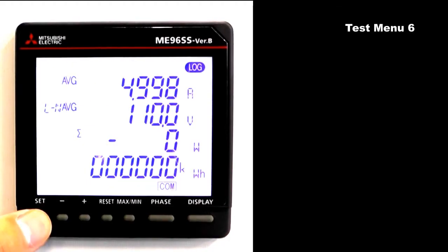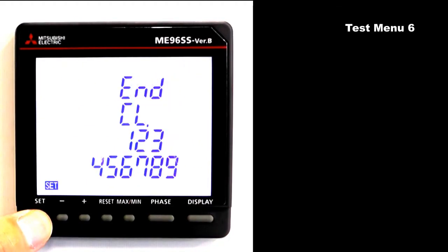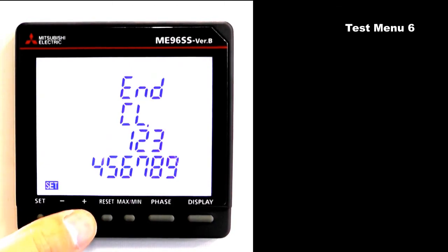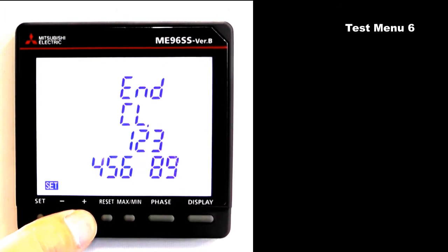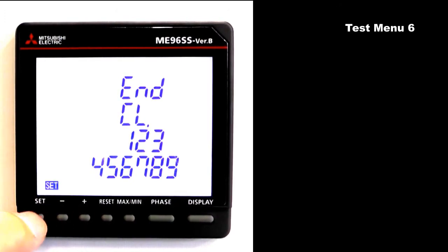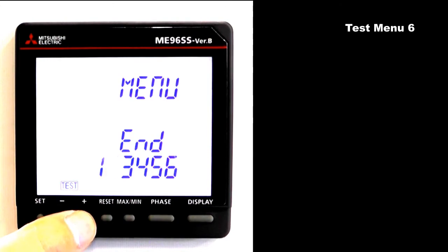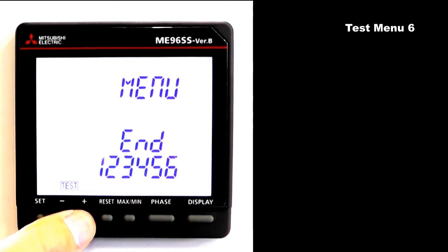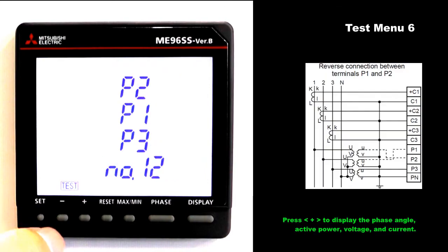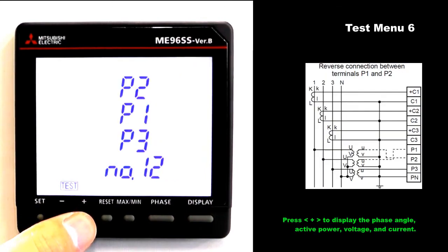Press and hold set for 2 seconds. Press plus to blink 9. Press set to move to the test menu. Press plus to blink 6. Press set to move to test menu 6. The last is an example of a reverse connection between terminals P1 and P2.